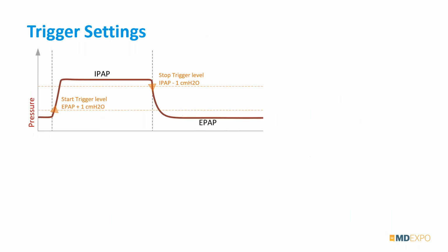So typically in a BiPAP ventilation, we have two pressure levels called IPAP and EPAP. And in such a situation, we would set the trigger for a start of an inspiration phase at the level of, like, this is EPAP, the lower pressure level, plus 1 centimeter of water pressure. And then a stop trigger when it drops from that IPAP level by 1 centimeter of water pressure.